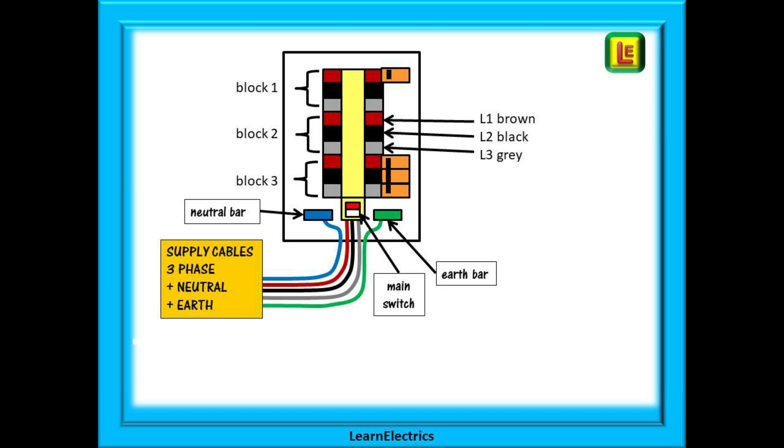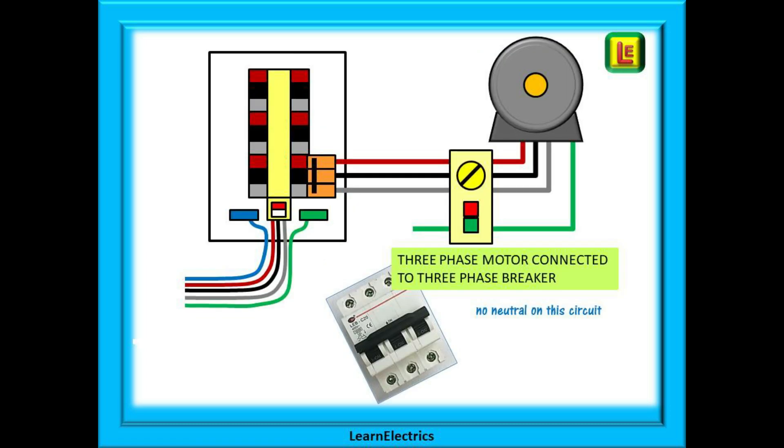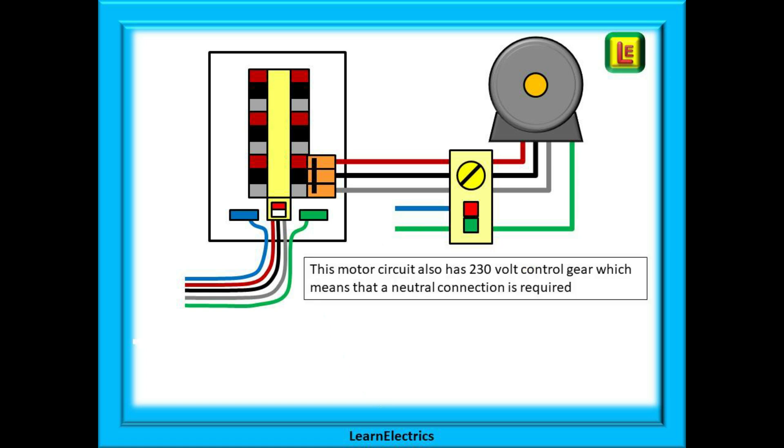We can populate this board with either single-phase circuit breakers or three-phase circuit breakers, as shown on the right-hand side of the board. Our first task is to connect a three-phase motor to the board. This is by means of a three-phase linked circuit breaker. If one phase has an overload or overcurrent and disconnects, then all three phases of that circuit will disconnect at the same time. This motor circuit does not require a neutral connection, so none is supplied. Some three-phase circuits will have 230 volt control gear, and this means that a neutral connection is also required.